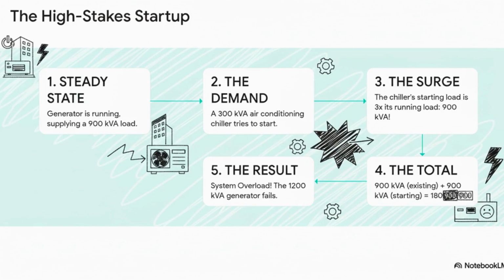For just a few seconds, that chiller needs 3 times its running power to get going, that's a surge of 900 kVA. So you add that to the 900 you're already using, and suddenly you're demanding 1800 kVA from a 1200 kVA generator. The result? Total system overload. The whole thing just collapses.